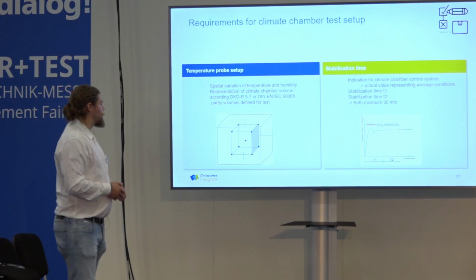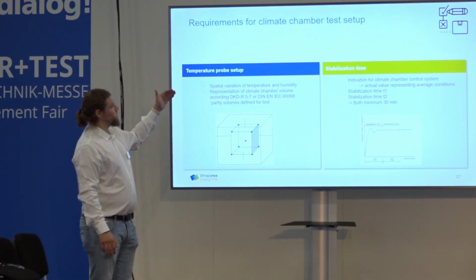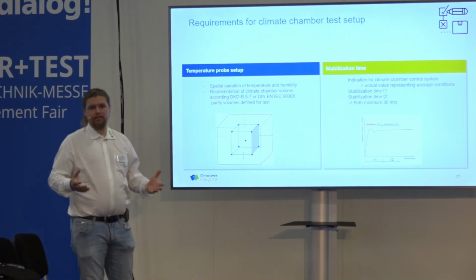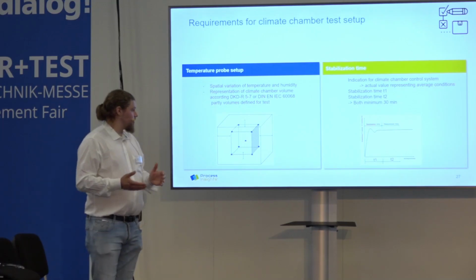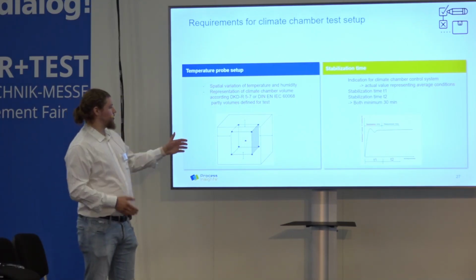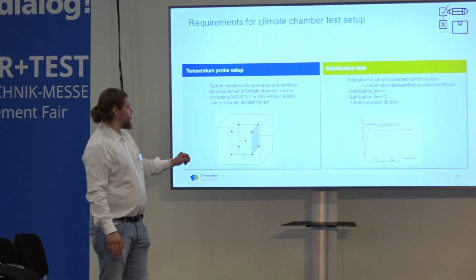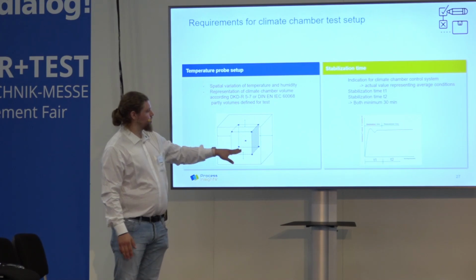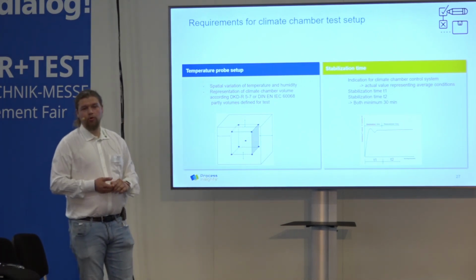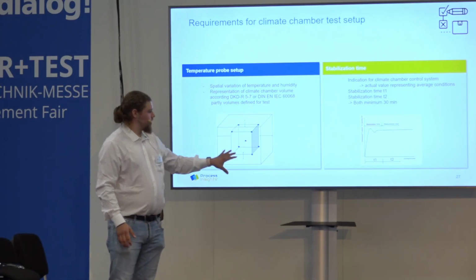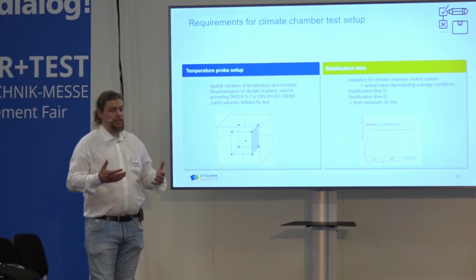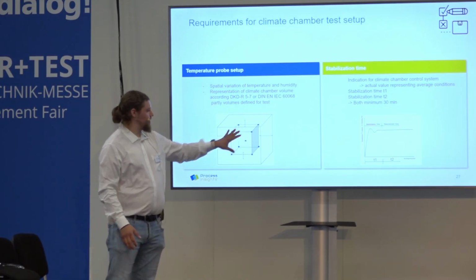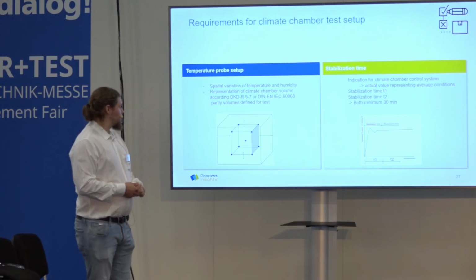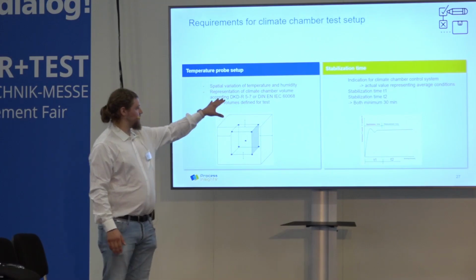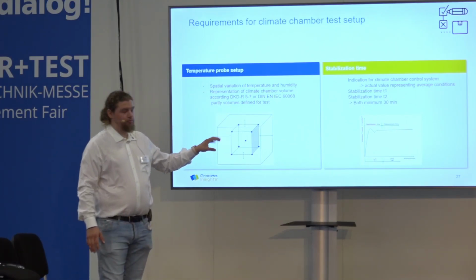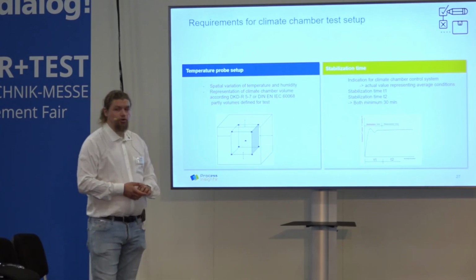To calibrate a climate chamber, it's important to know that we have spatial variations of temperature and humidity. We need to define them to find the representative value for this chamber. We have the total chamber volume, and then the useful volume, which is the one represented after the calibration. So not the full volume is calibrated, but the one defined here. Therefore we have fixed points defined in the standards where we have to locate our temperature probes, and where we also should place our humidity measurement accordingly.